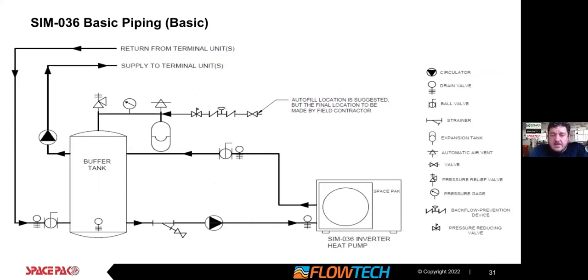The basics on SpacePak's monoblock and split systems here, feeding a buffer tank with a 3-ton unit. As I mentioned, pay special attention to sizing that circulator. A common fault we have is that it's undersized. We have the pressure drop through the unit, we have the piping, we have a glycol percentage derate. So make sure that is sized appropriately, feeding the unit and feeding the buffer tank.